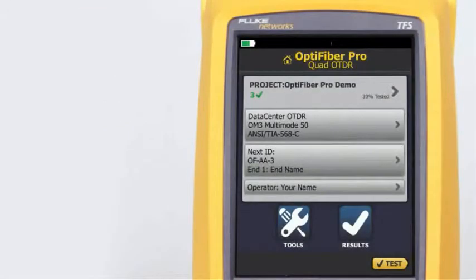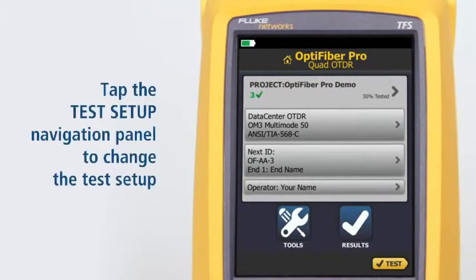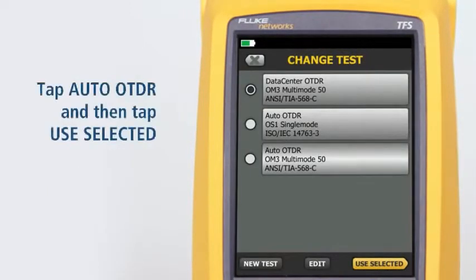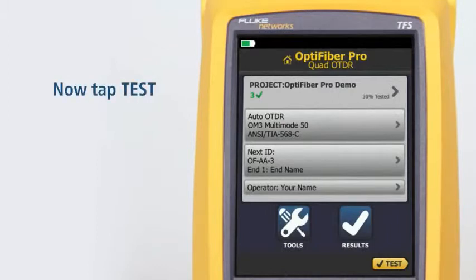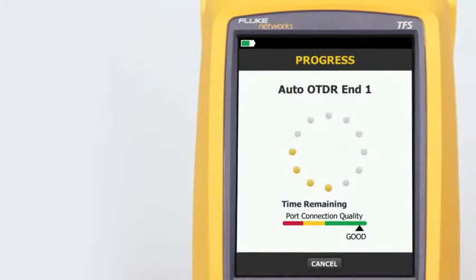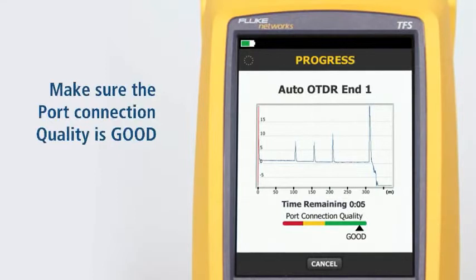The Auto OTDR test mode automatically selects settings that give you the best combination of test time, dynamic range, and resolution. It provides the best view of the events on the cabling, and is the easiest to use — the best choice for most applications. The previous test was run using the Data Center OTDR setting. Tap the test setup navigation panel, tap Auto OTDR, and tap Use Selected. Now simply tap Test and the tester will determine the best settings to use for the fiber under test. Make sure the port connection quality is good; if it's not, the tester's ability to properly analyze the fiber may be impaired.